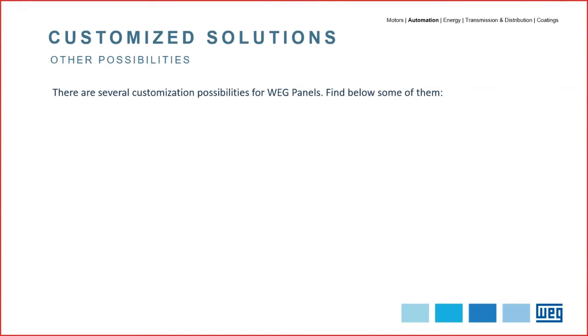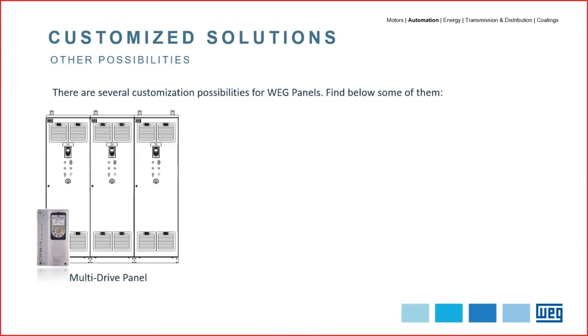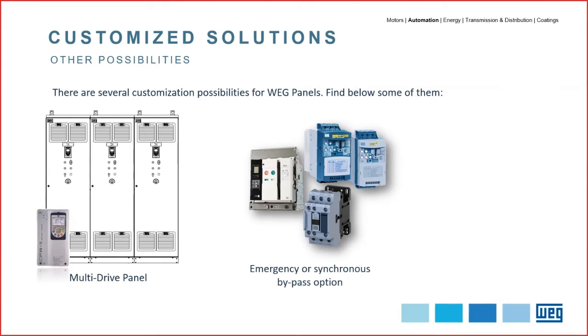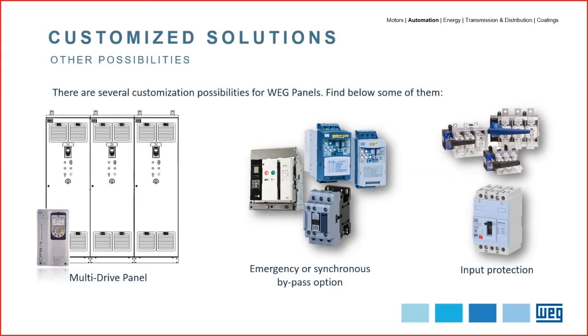There are several additional customization possibilities for WEG drive panels. Some of them are the multi-drive panel, where the multi-drives are installed in a single panel, and this configuration actually protects the electrical components and gives a simple application all the advantages of a panel structure. Emergency or synchronous bypass options. This configuration may be built with contactors, ACBs, or air circuit breakers, or also soft starters, depending on the requirements. Customized input protection, being possible to choose between circuit breakers or fuses as part of the input protection circuit.